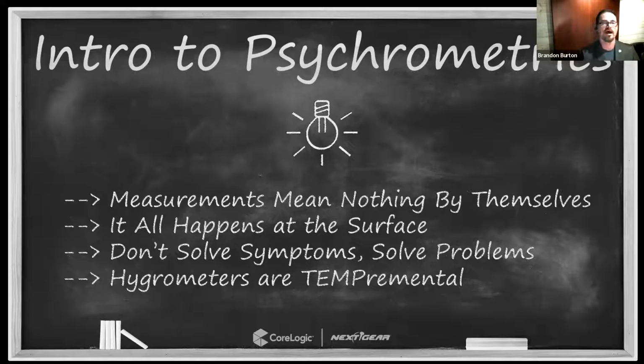Hygrometers have to acclimate, right? They have to get comfortable in the space, right? You got to give them time. They've got to come up to temperature. The whole body of the meter has to warm up to that room temperature to truly be effective, which takes time, right? A really good thermal hygrometer, 60 seconds to 2 or 3 minutes, somewhere in that range, as long as the temperature wasn't too extremely different. $200 hygrometer, $300 hygrometer, you're talking about 10 minutes. $20 hygrometer, you're talking about never, all right? So it's really important to make sure you give them the time to acclimate to the space.